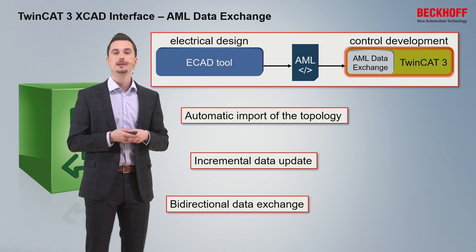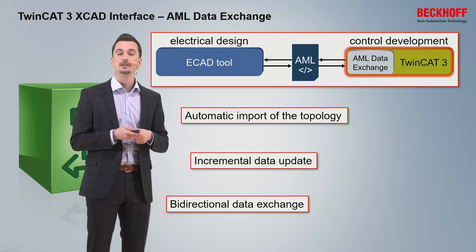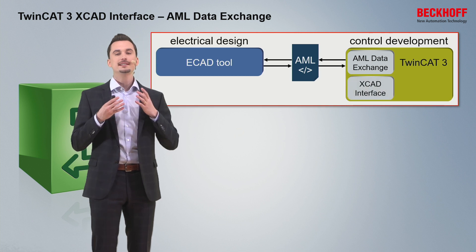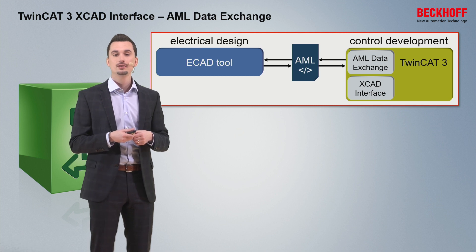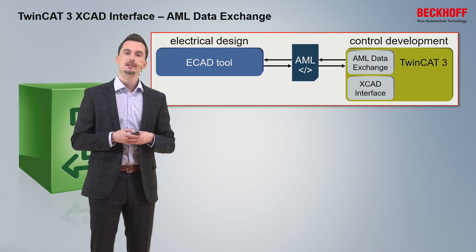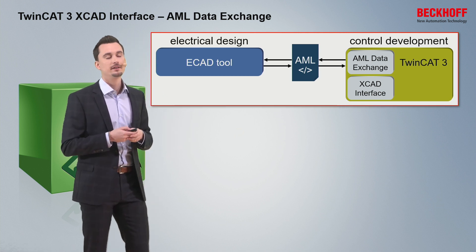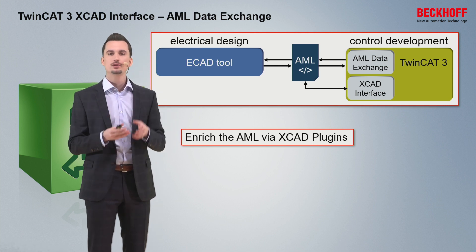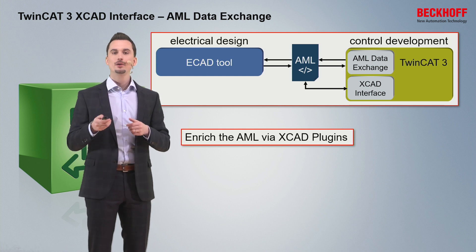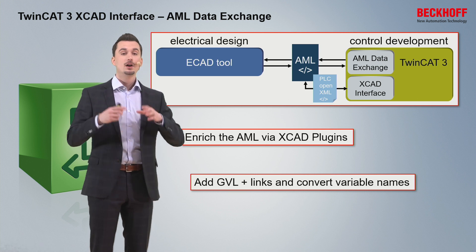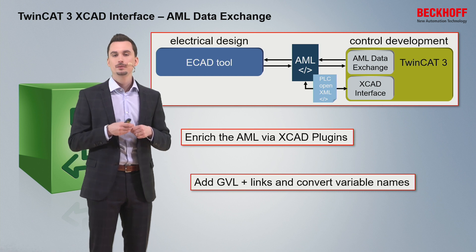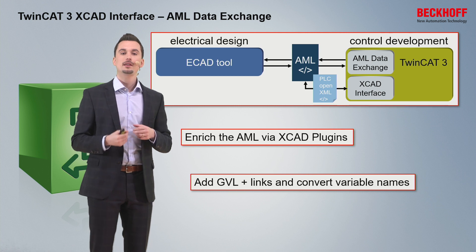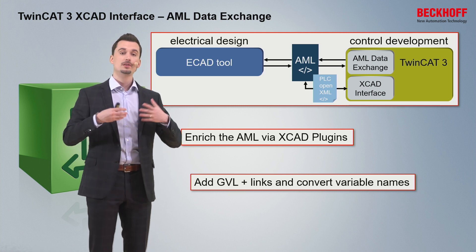On top of this workflow, we have now added the new XCAD interface version, which uses internally the AutomationML Data Exchange to import and export the IO topology. In addition, we are now adding further functionalities with the help of so-called XCAD plugins — it is possible to enrich the AutomationML file. We have predefined plugins available, for example to create a global variable list, add variables based on a tag table available in the AutomationML format, and also automatically connect those PLC variables with the IOs in the IO topology — so the links are automatically created.